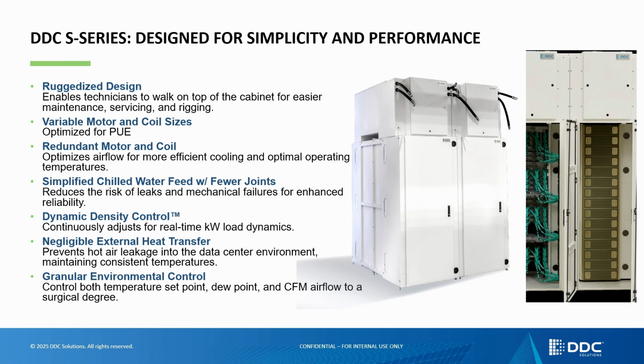In the original version of the cabinet, this was air-cooled with liquid heat exchange, where liquid can't get from the top portion of the cabinet, where the heat exchange is done locally, into the IT environment. So very safe. There's also no fan walls required. These systems plug directly into the existing building water loop.